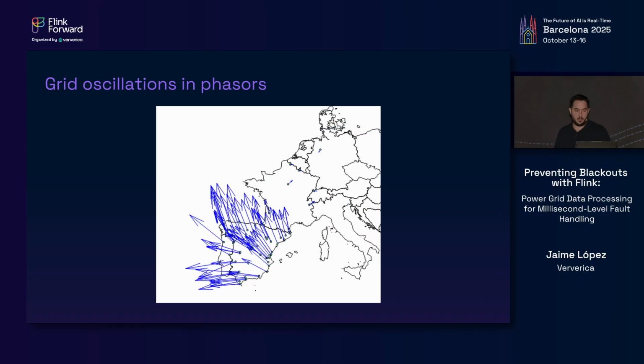We're talking about phasors. When you see how quickly these oscillations spread in the grid, you see that the phasors that are measured at different points in the grid suddenly start to go completely out of whack. The nominal frequency and voltage shows us a dot that has no vector attached to it. And this is what happened in Spain during those 5 seconds. Everything went haywire. Even though the outage happened around here, you can see that all over here, 1,000 kilometers away, things were going out of control already within those 5 seconds. These are chain reactions. And the only way to stop the chain reaction is to be very early at the beginning of it and stop it before it spreads.